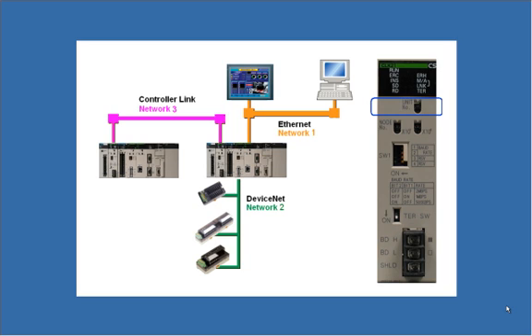Each network module has a single rotary switch marked Unit Number. This unit number sets the internal addressing used by the network module and must be unique for each network module on the PLC backplane.